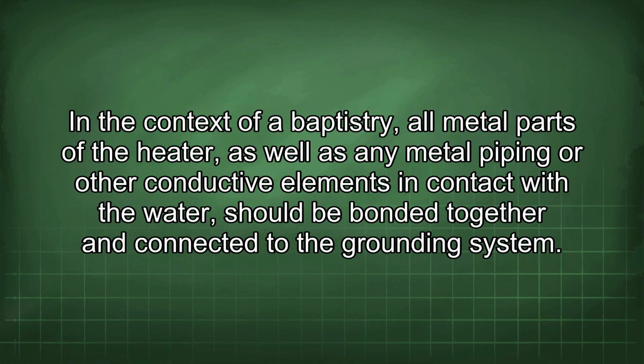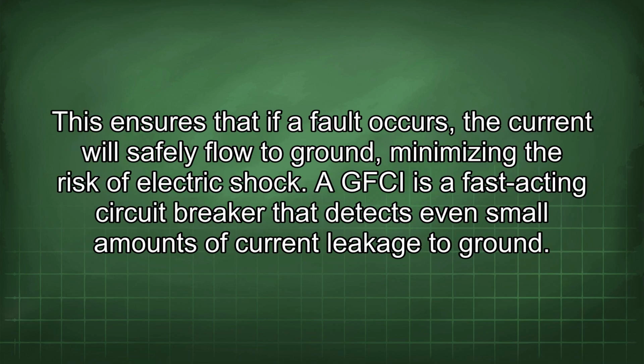In the context of a baptistry, all metal parts of the heater, as well as any metal piping or other conductive elements in contact with the water, should be bonded together and connected to the grounding system. This ensures that if a fault occurs, the current will safely flow to ground, minimizing the risk of electric shock.